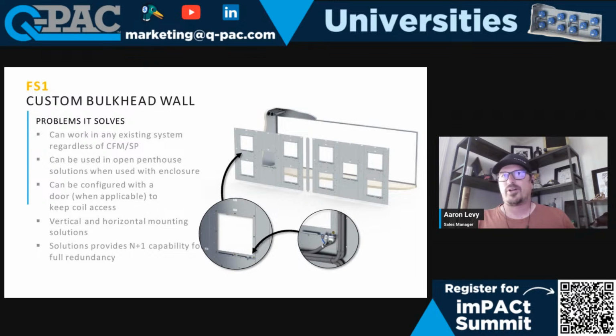We can configure bulkhead door arrays with a custom door if needed. When we're removing a lot of those old systems with double width, double inlet blowers or vane axials, sometimes we lose access to the coil side of the section. By allowing us to add a door to a solution when applicable, mechanical contractors still have access to the front of that coil for maintenance or cleaning. We'll put that under a specials category when designing the system, but understand that's a potential application we can do.